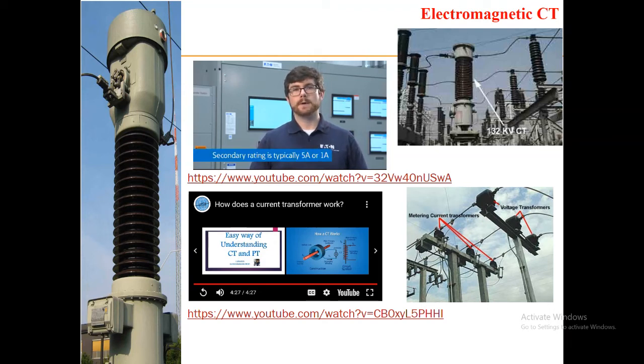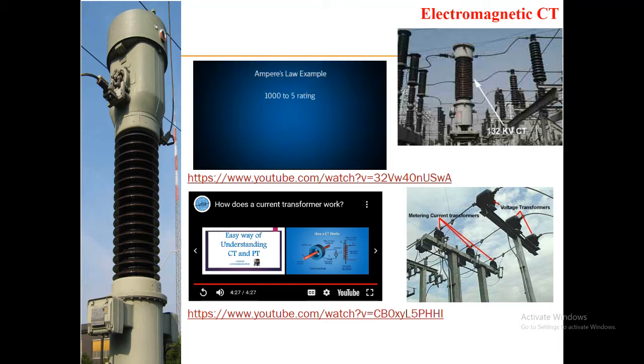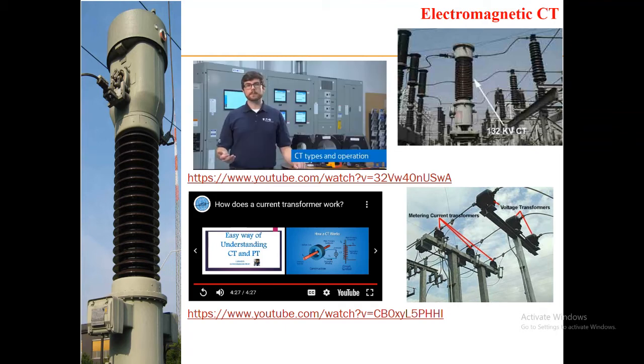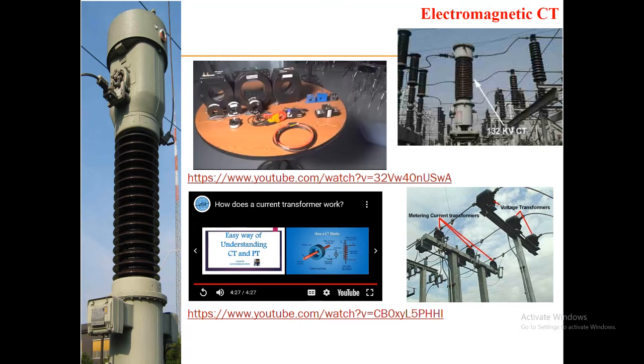The current on the secondary winding is proportional to the current flowing through the center of the core. Typically, the secondary rating is 5 amps or 1 amp. For example, with a 1000 to 5 rating or a turns ratio of 200 to 1, when 1000 amps flows on the primary circuit, 5 amps would flow on the secondary winding.